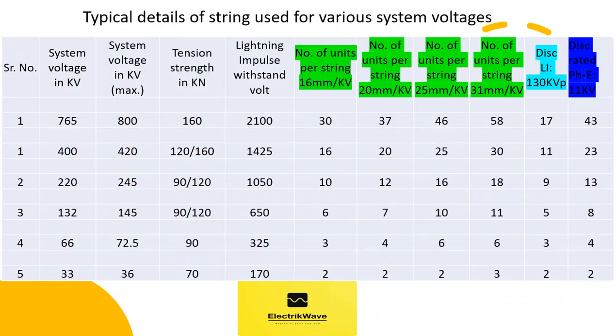Here, typical details of strings used for various system voltages are tabulated for creepage values of 16 mm/kV, 20 mm/kV, 25 mm/kV, and 31 mm/kV, with disk lightning withstand voltage of 130 kV peak and disk rated voltage of 11 kV.